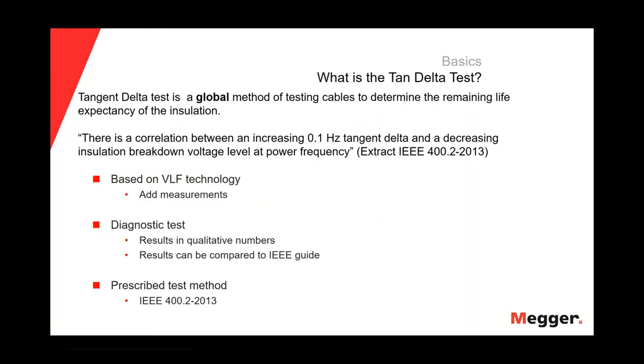So what is the tan delta test? Well, we can say that the tan delta or tangent delta test is a global method of testing cables to determine the remaining life expectancy of the insulation. We know that there is a correlation between an increase of 0.1 hertz tangent delta and a decreasing insulation breakdown voltage level at power frequencies. That is something that we know. So the tan delta test is based on VLF technology, is a diagnostic test that results in qualitative numbers, and we can also compare the values of the tan delta with the IEEE guide, and of course the tan delta is a prescribed test method by the IEEE 400.2.